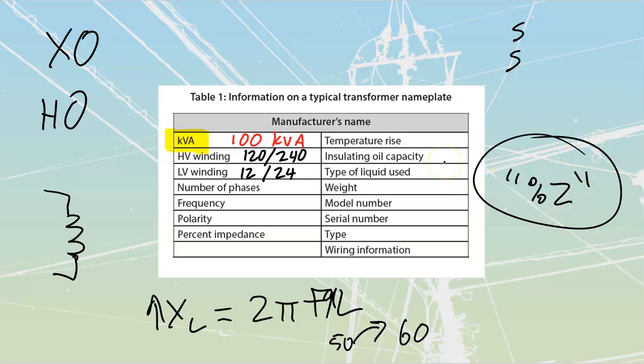We'll cover the formula later as well, but that is going to tell me how many amps it's going to put out under fault. So I need to make sure that my circuit breaker can clear it. Everybody should be familiar with the fact that circuit breakers are rated for, let's say, 50 amps, but then they have an interrupting or fault rating of like 10,000 amps that they can interrupt. You'd want to make sure that whatever your transformer is, that high rating, the interrupting rating, could be broken by it. We're also going to need to use that percent impedance to make sure that we can parallel two transformers so that we don't end up overloading one.